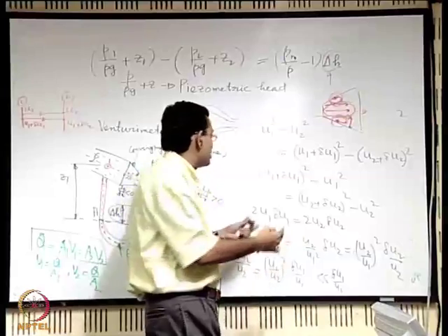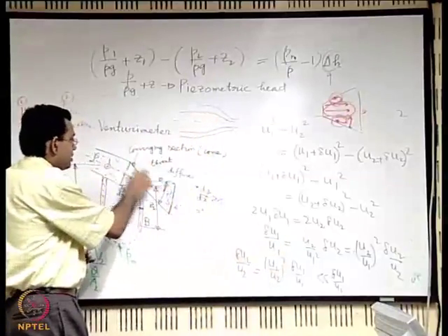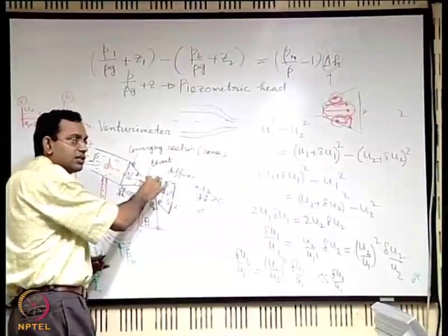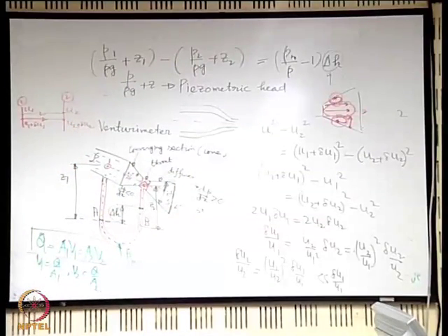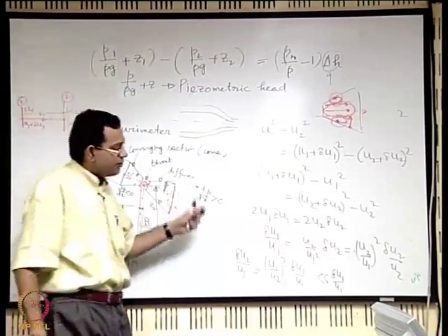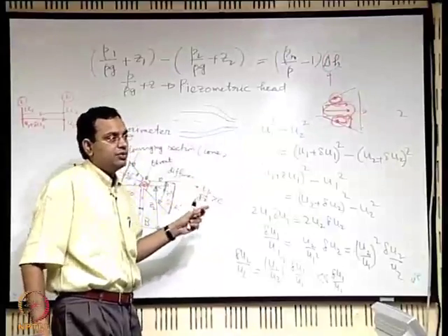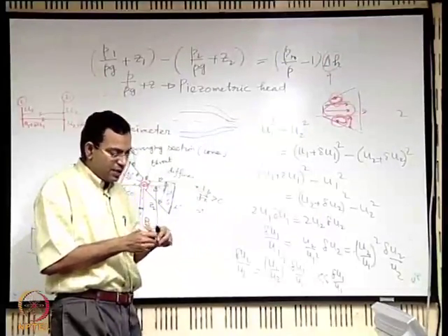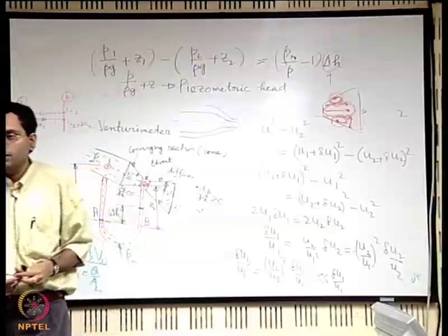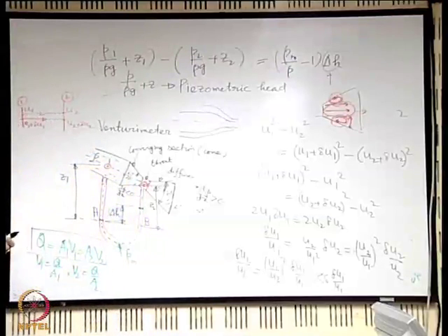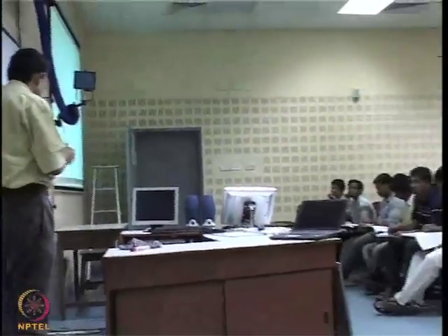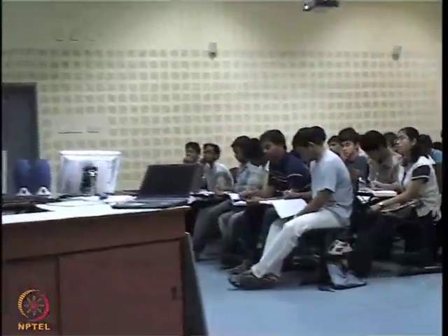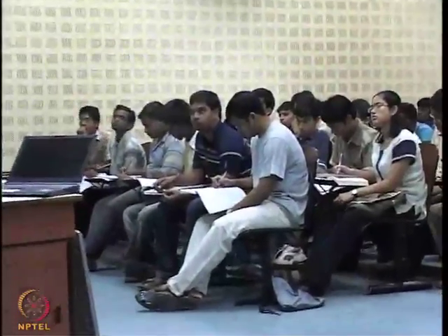If one designs this device well by minimizing losses, the coefficient of discharge — ratio of actual to ideal flow rate — is very close to 1, around 0.97 to 0.98. Some non-idealities are taken care of by the continuously converging section and the properly designed diffusing section. The Venturimeter is a common device used in pipelines to measure flow rate, but it is not very inexpensive. For very routine applications, one might look for cheaper devices following similar principles.